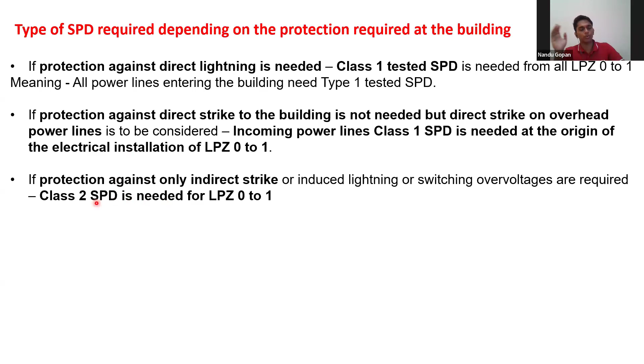Now, if you want protection only against indirect strikes, and you don't want direct strike protection on overhead lines or for your building, and you care only about indirect strikes, which are quite common, then you can put type 2 SPD. You don't need to worry about type 1 at all. You can leave type 1 and put type 2 SPD everywhere, zone 0 to 1, 1 to 2, 1 to 3 to 4, it depends.